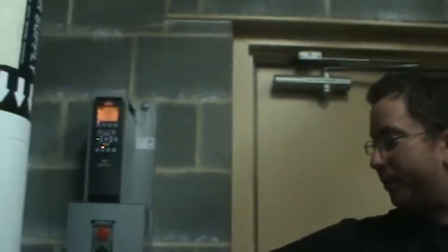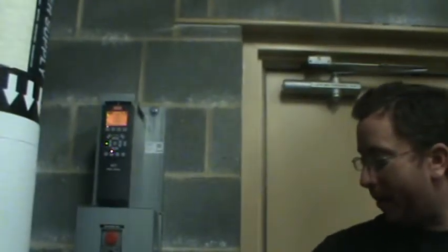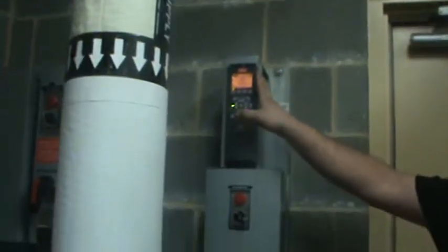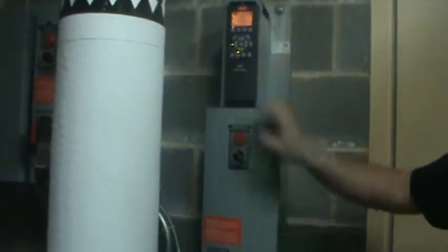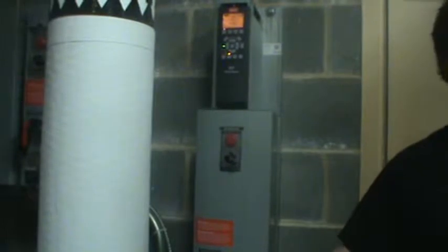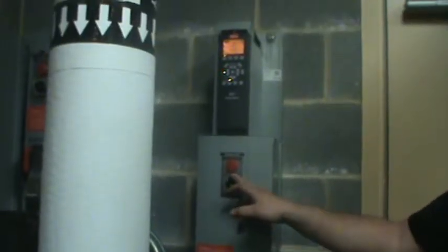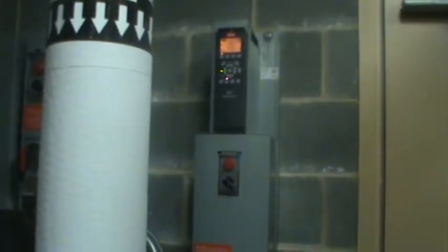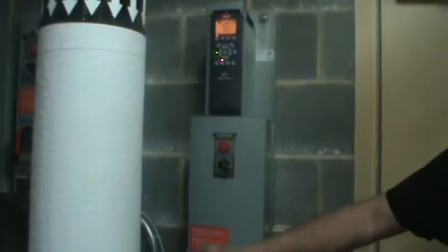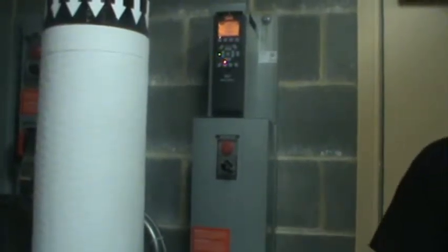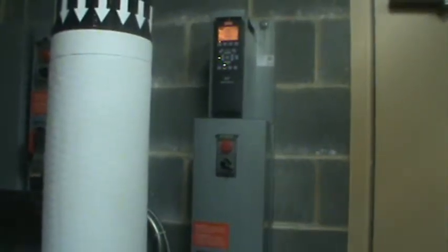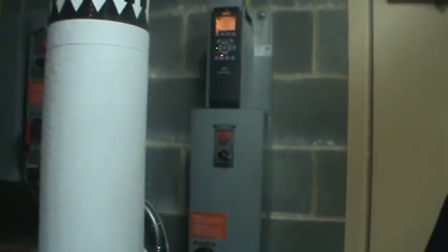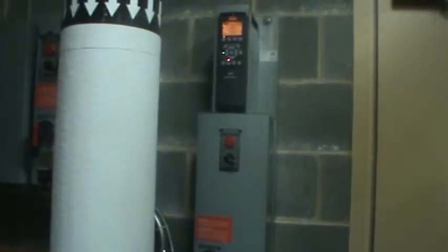There is a set of fuses in here. There are basic contactors in there. Really the way this works is power comes in, just to extend a contactor up into the drive. The speed is manipulated and then sent back out to the drive, out to the motor. In the bypass mode, it's basically a real hard, non-stop starter. Power comes in here, contactor, out. No control, no nothing. Hard start, boom, go. Run until somebody turns it off.